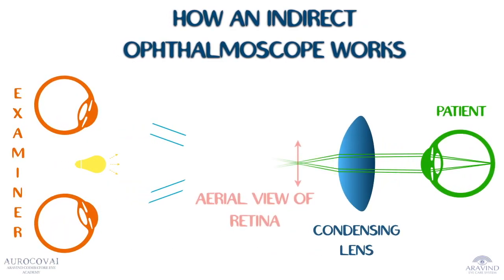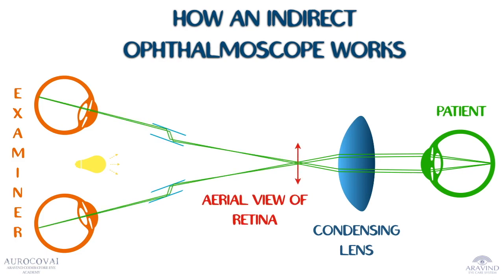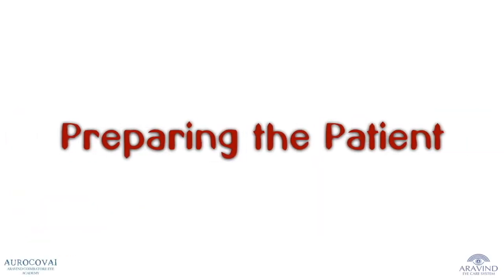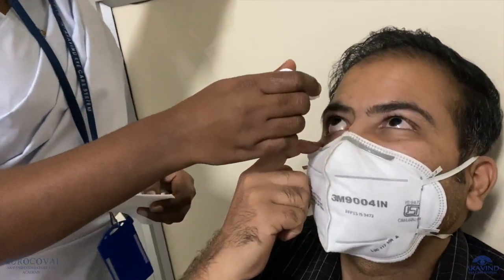The basic principle of the indirect ophthalmoscope is to make the patient's eye highly myopic by placing a strong convex lens in front of it. The emergent rays form a real inverted image between the lens and the observer's eye. Binocularity is then achieved by artificially reducing the observer's IPD from 60 millimeters to approximately 15 millimeters by the help of prisms and mirrors.